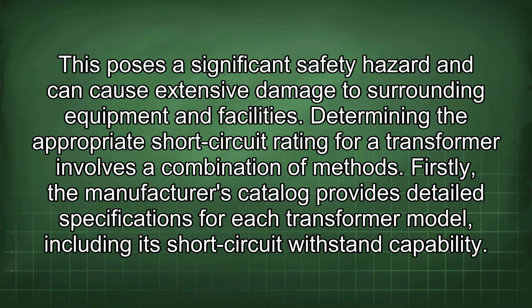Determining the appropriate short-circuit rating for a transformer involves a combination of methods. Firstly, the manufacturer's catalog provides detailed specifications for each transformer model, including its short-circuit withstand capability.